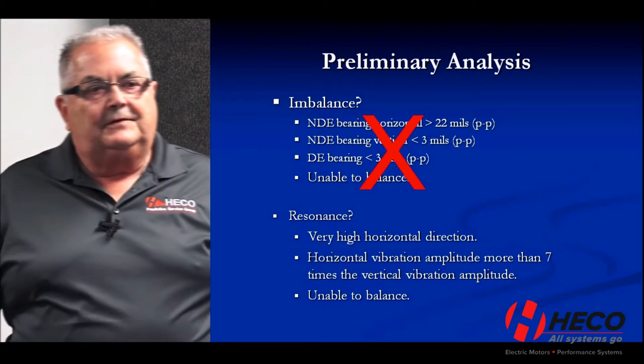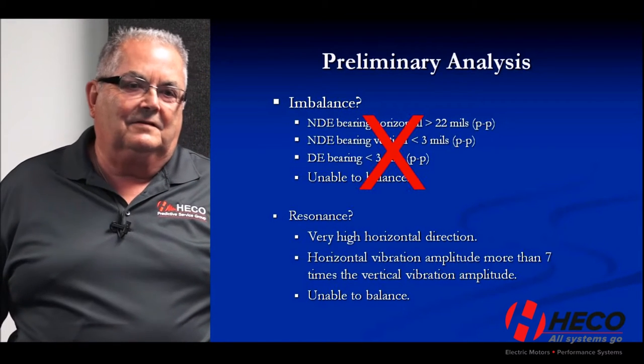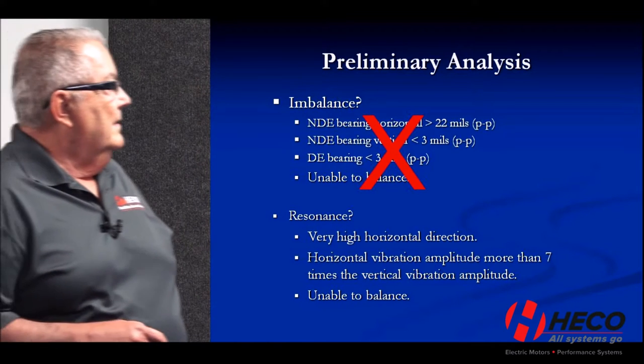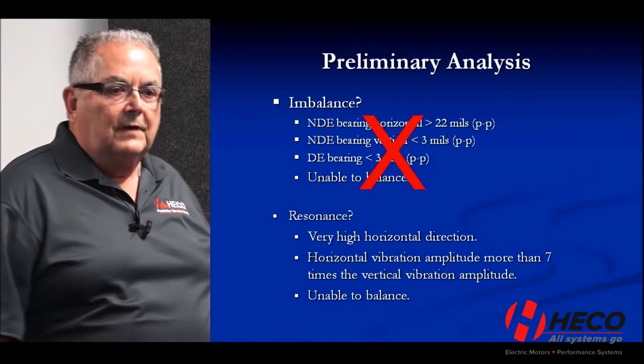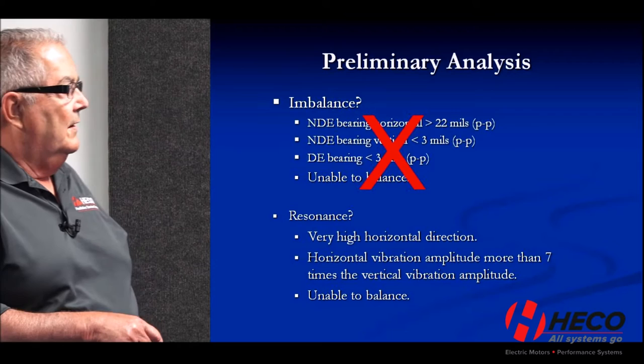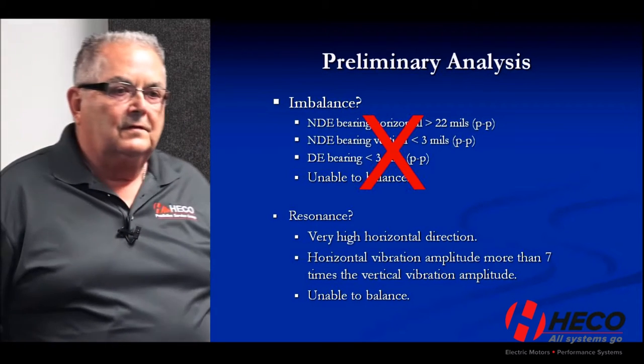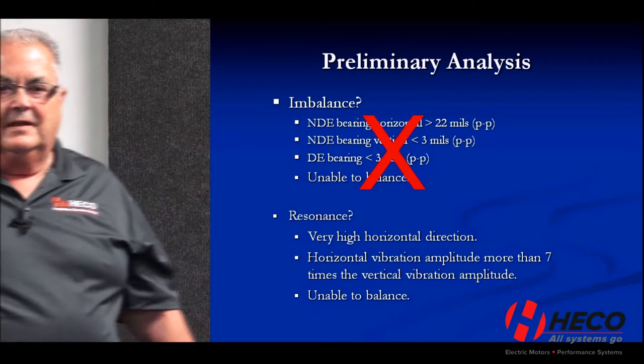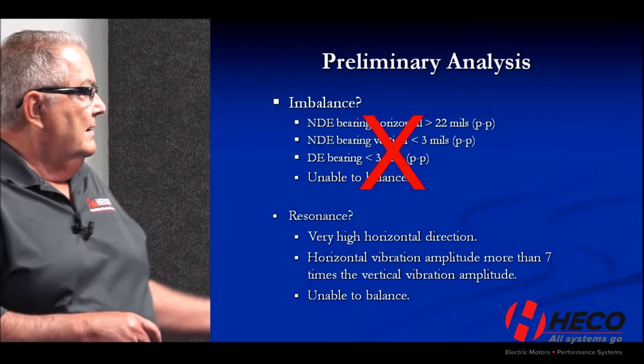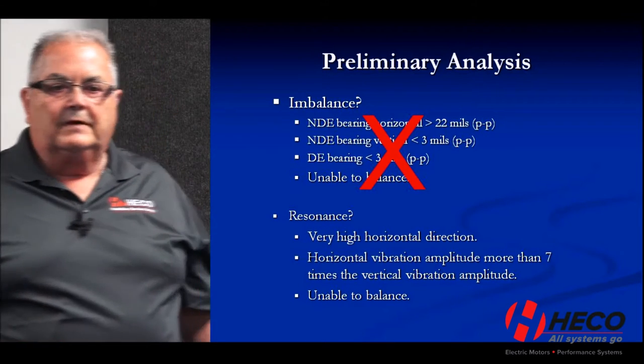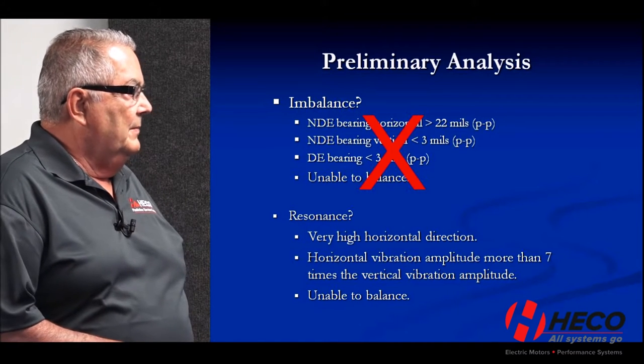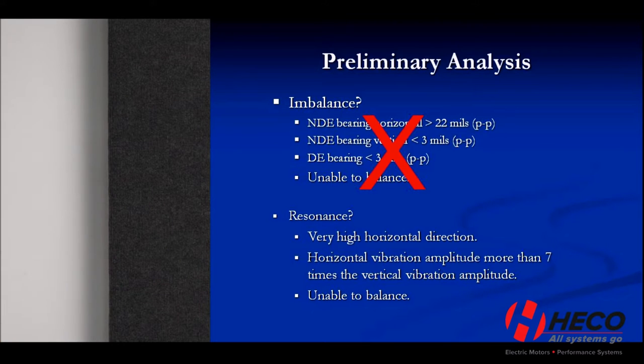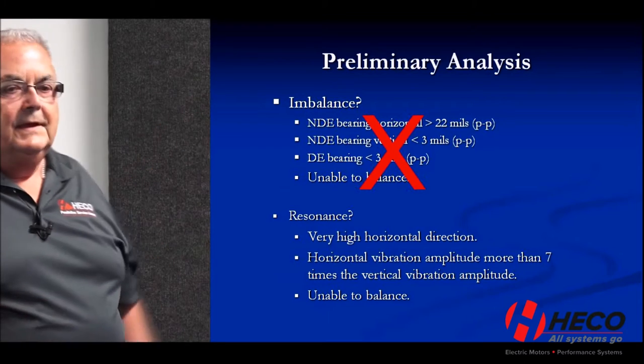So what might be the cause? Imbalance is certainly one possibility, but if he's a tech rep from the fan supplier, there's a good guess he knows how to balance fans. The other hypothesis was a resonance condition — supported by the very high horizontal vibration compared to vertical. I use a rule of thumb: if vibration is four or five times higher in one direction than the other, I'm suspicious of a resonance issue. In this case the ratio was more than seven to one, and he was unable to balance it out.